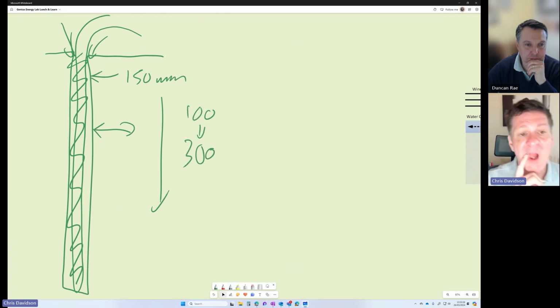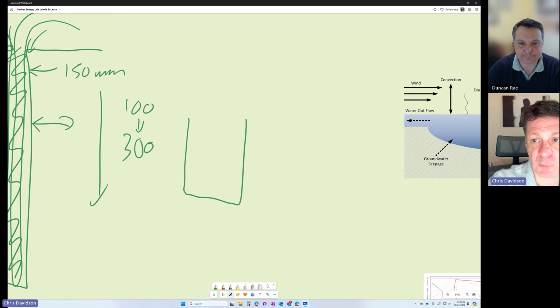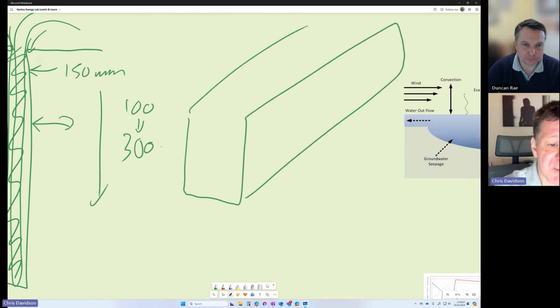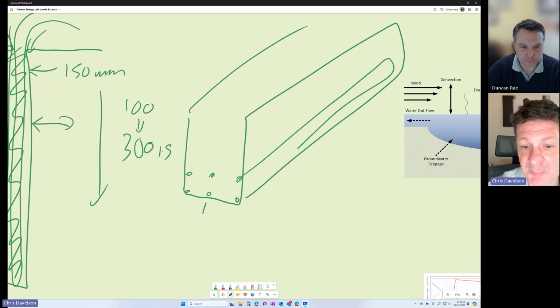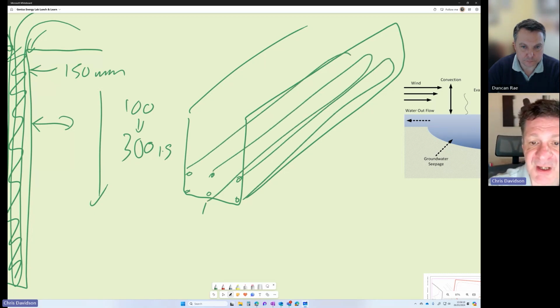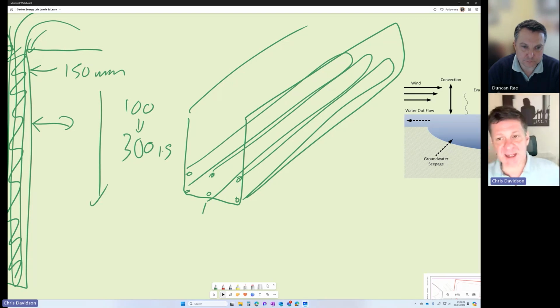Okay. There are other closed-loop options available to us, principally being horizontal trenches, which are just trenches dug in the ground. In the UK, we tend to be 1.5 meters deep and 1 meter wide, and I tend to like what's called 6-pipe trenches, which are straight loops of pipe put inside the trench and buried. You'll often see in magazines coils of pipe, slinkies, which tend to be okay for smaller domestic systems, but anything commercial or multi-residential, schools, for example, tend to have these types of systems. We can go with a horizontal straight pipe trench like that. Obviously, more space is required for horizontal trench systems than for vertical borehole systems.